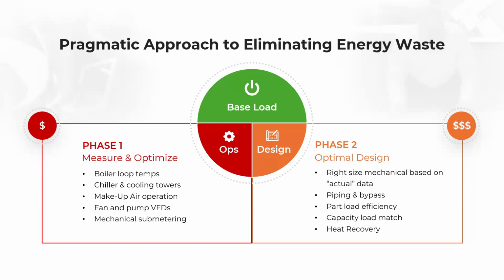Chillers and cooling towers: maintaining the right flow rate through the chillers and maintaining the right chiller and cooling tower set points so that the delta T's can be maintained. That's one of the biggest problems with chillers and cooling towers. We overpump them through a combination of not optimizing the VFD speed on the pump and not optimizing the set points, and that causes low delta T's. Low delta T's on chillers and cooling towers are very inefficient.